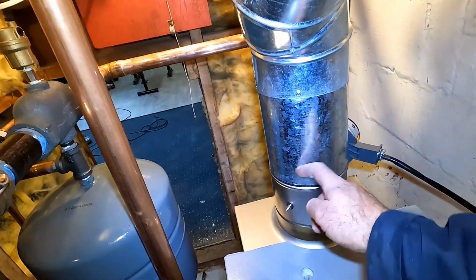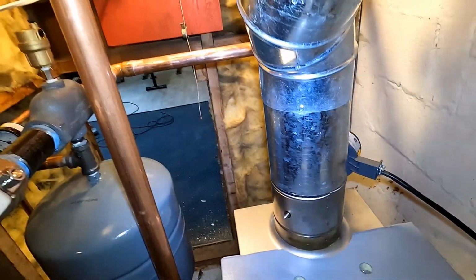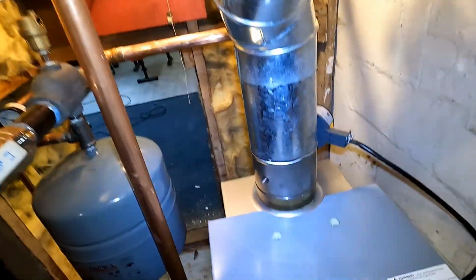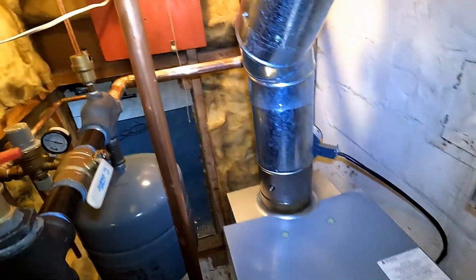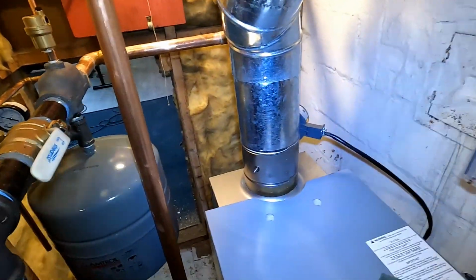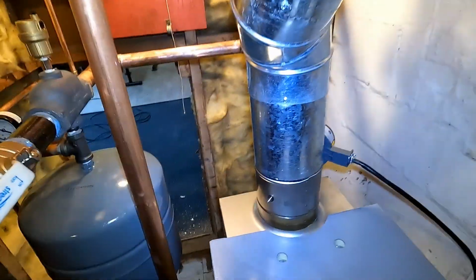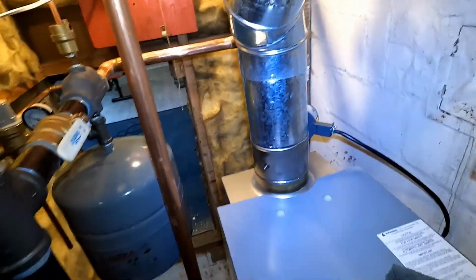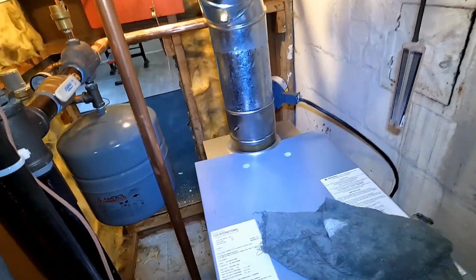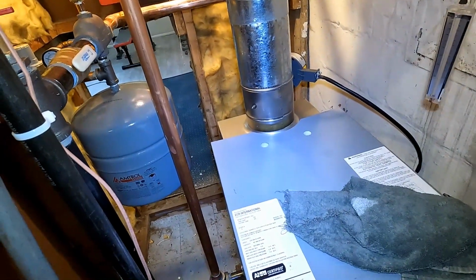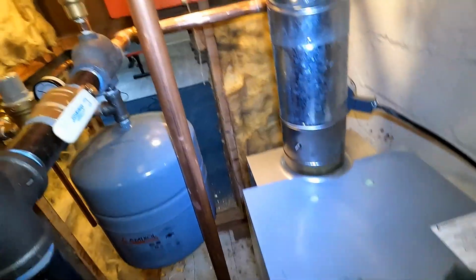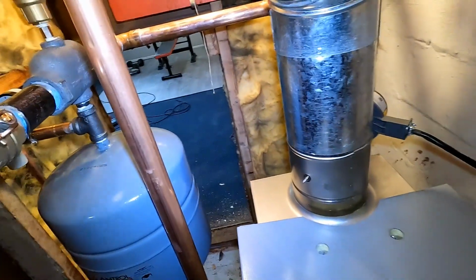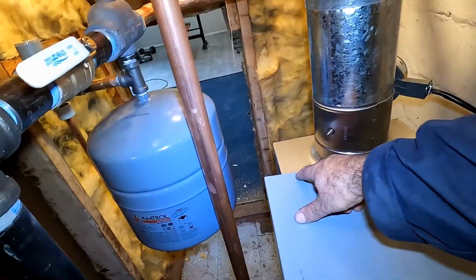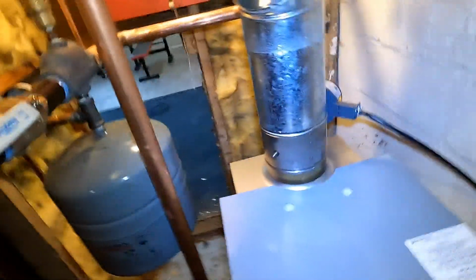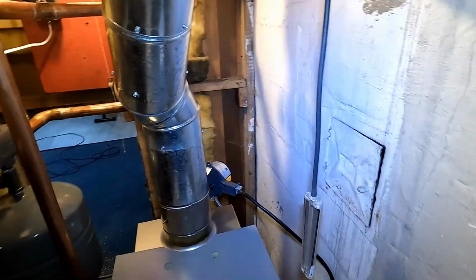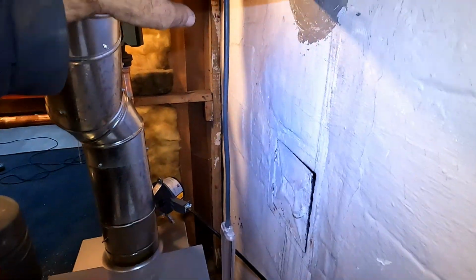The only time you would put the probe down here is if this is connected to the vent. The boiler is connected to its vent, like a power burner, oil burner, or a modification of a gas draft box that gets sealed off to make the appliance safe with a barometric damper. You do not take a draft reading before the dilution air gets in. It gets taken after the dilution air up here.